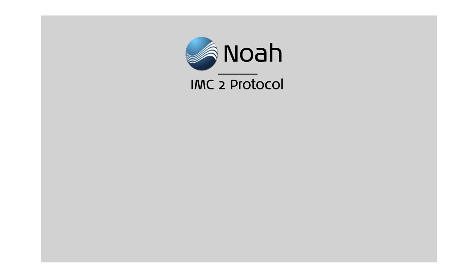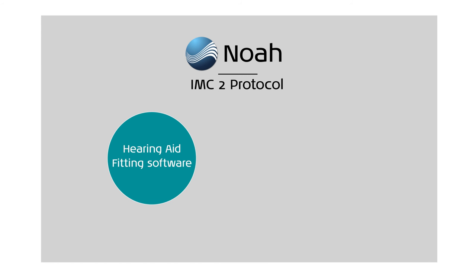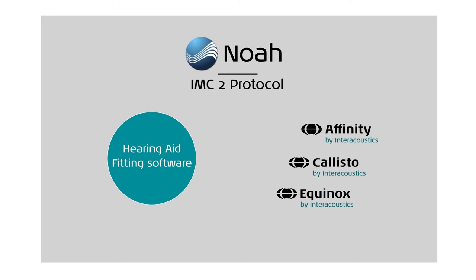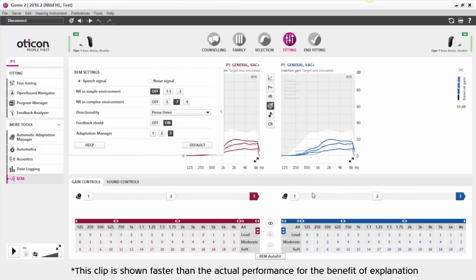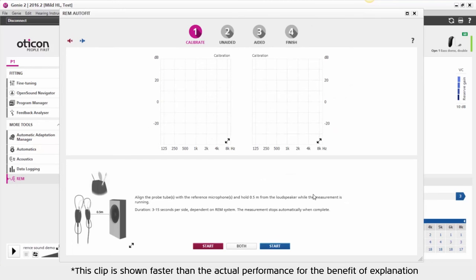IMC2 handling. In the recent update to NOAH 4, they've included an update to the intermodule communication protocol. In short, this protocol enables a common format which allows hearing aid fitting software to control diagnostic software. We've utilized this new function and included it within the newly updated version of our suite to allow an automatic REM procedure in cooperation with Oticon. This combined feature from Oticon and Interacoustics optimizes the procedure required for REM measurements.